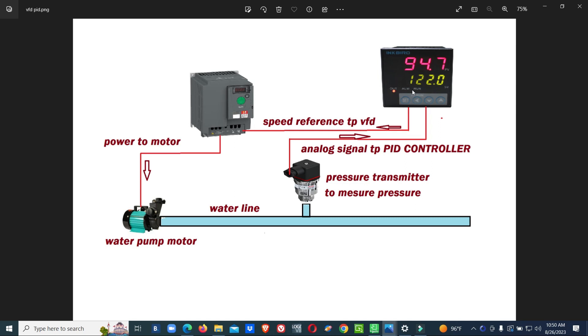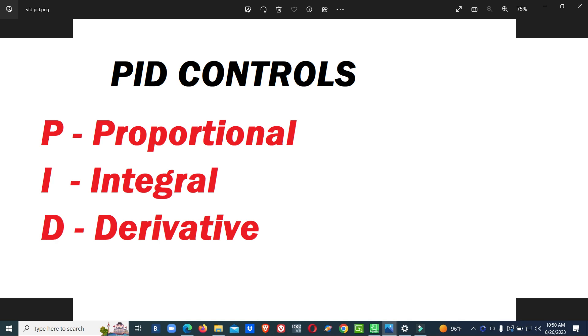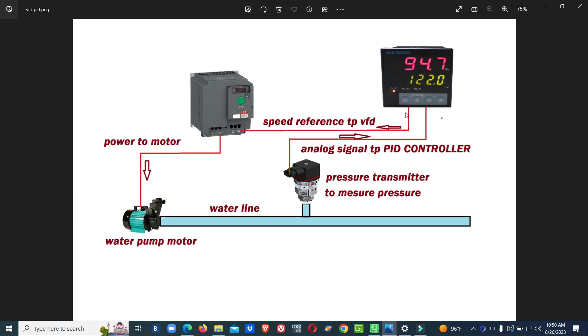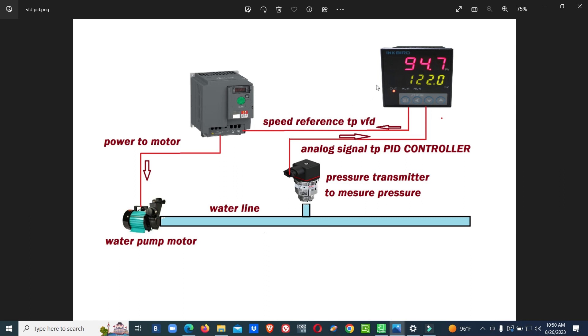A PID controller is a Proportional-Integral-Derivative controller. In a single PID controller, there are three different functions or controllers combined: the Proportional controller, the Integral controller, and the Derivative controller. After PID controllers were implemented, many devices came with inbuilt PID controllers — for example, a VFD has an inbuilt PID controller. Instead of a separate PID controller, we can connect the pressure transmitter signal directly to the VFD and make the PID control settings in the VFD to control the pump directly.